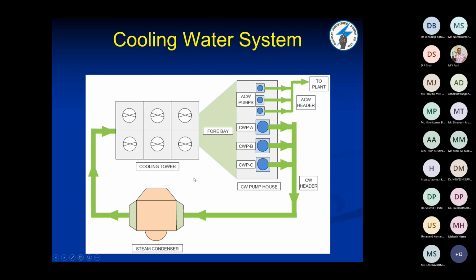Now this is the system. This is the cooling tower. This is the steam condenser. This is a CW header. This is ACW, that is auxiliary cooling water, that goes to the different auxiliaries like boiler feed pump and such things. And this is the cooling water header. There are 3 pumps: CWA, CWB and CWC. All these pumps go to the common header and that goes to the condenser. And from the condenser outlet, that water is going to the cooling tower. And from the fore bay, this is the circuit.